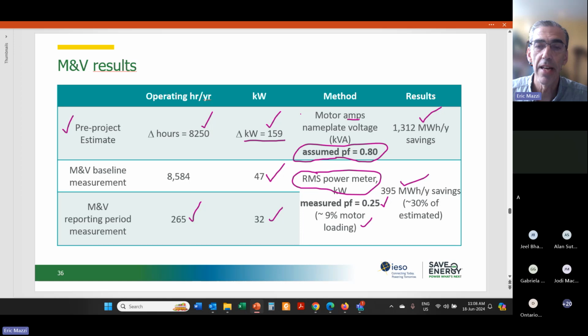And so you could say there was some time and resources attempted to be saved in the pre-project by just using motor current readings, spot readings, to estimate the baseline power. But as it turned out, it was overestimated by more than a factor of 3 what the real power consumption was. And so therefore the savings came out at about 30% of what was estimated for the purposes of the incentive.